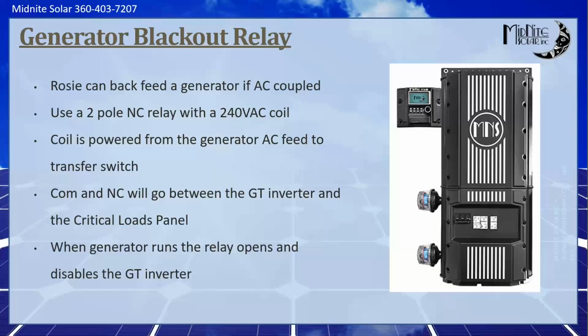And this is where, if it's AC coupled, we need to get into what we call a blackout relay. Because remember, the Rosie, just like any other battery-based inverter, if you connect an input to its input, it's going to close its relay. And once it closes its relay, it connects the grid tie inverter to that input, which in this case is now a generator. And most generators do not appreciate being backfed from the grid tie inverter, especially if it's a small wheels and handles style generator. So what we normally do is we use a 2-pole, normally closed relay with a 240-volt coil. What I do is I just tap right in my transfer switch, and I take the 240 volts from the generator, feed it to the coil of the relay, and then the contacts in the relay I use to break the generator feed to the grid tie feed to the sub panel.